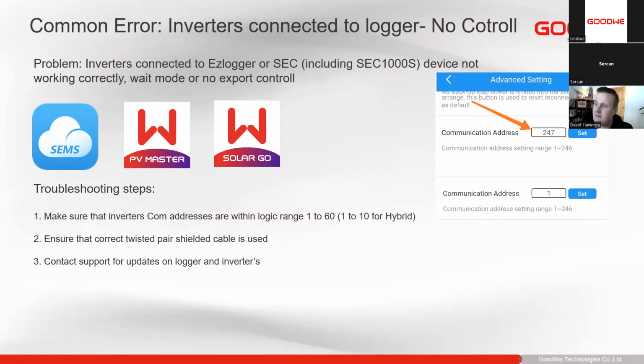So when we set our on-grid inverters, we typically only set the grid code, we made sure our time is correct, we made sure our grid type is correct, and then we make sure our communication address is set for the RS485. So that communication address for the on-grid inverters should always be in the range from 1 to 60, and for the hybrids from 1 to 10. Please always make sure that we have set them and no two devices have the same address. So for on-grids 1 to 60, for the hybrids 1 to 10.